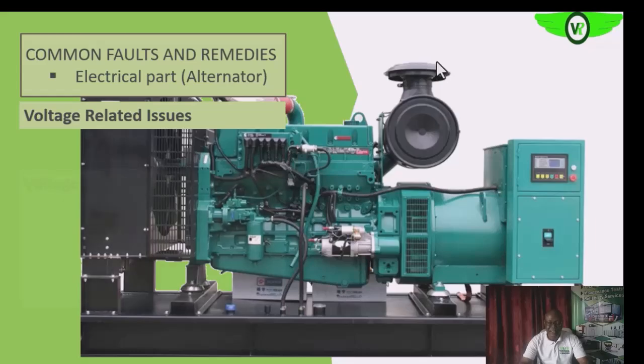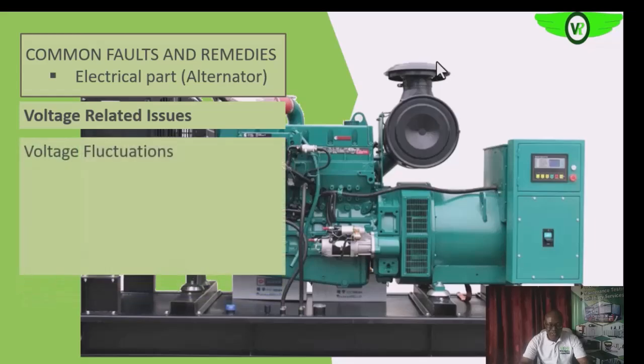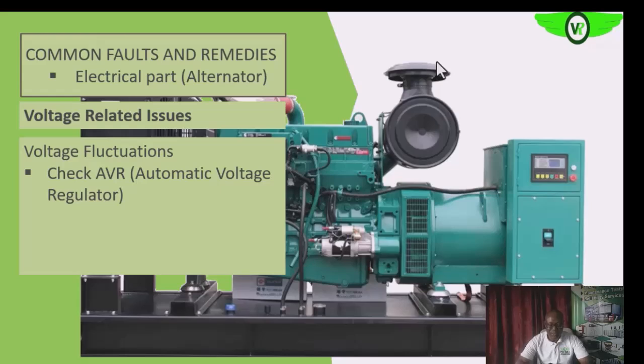The first is voltage fluctuations — that is, the voltage is going up or down. If that is the case, we want to check the excitation system. The AVR could be delivering an inconsistent current.